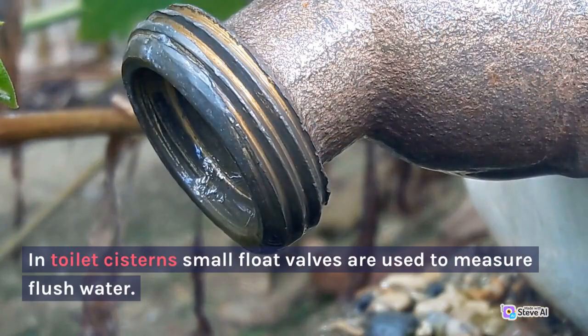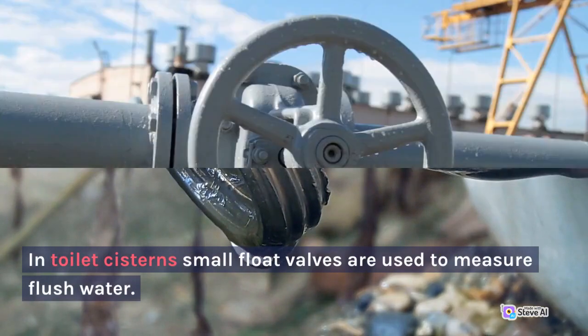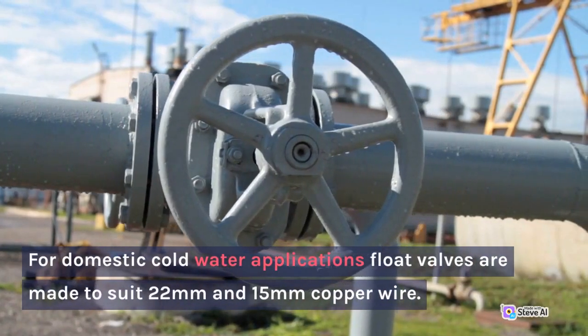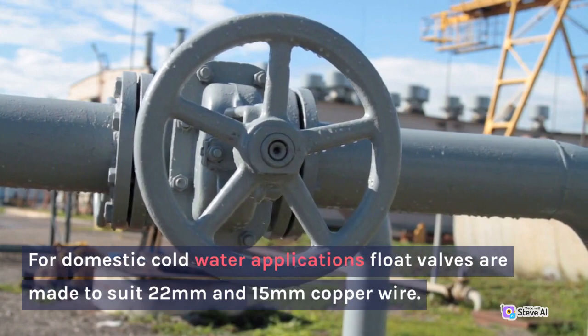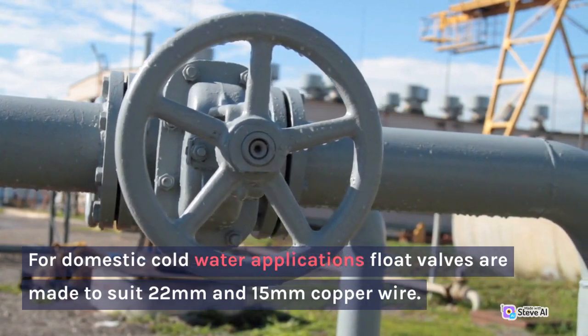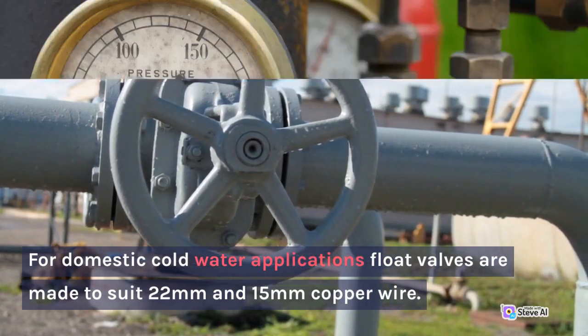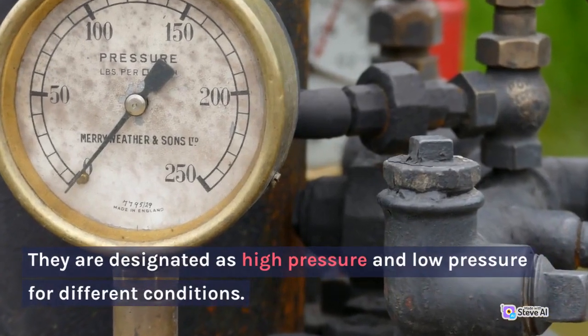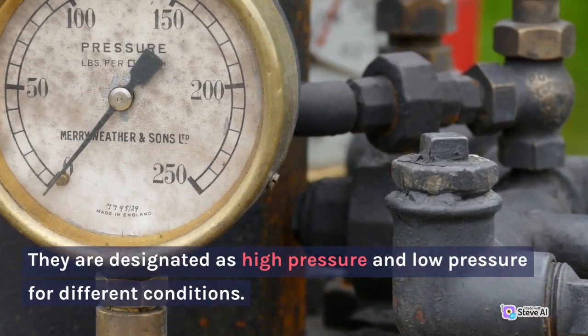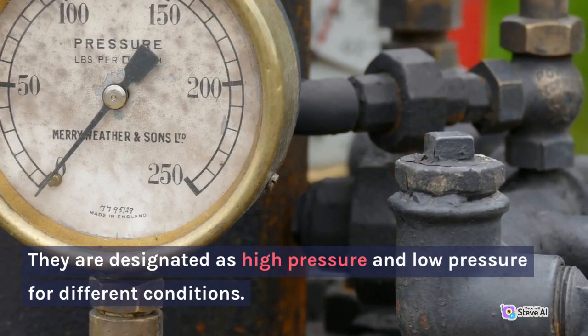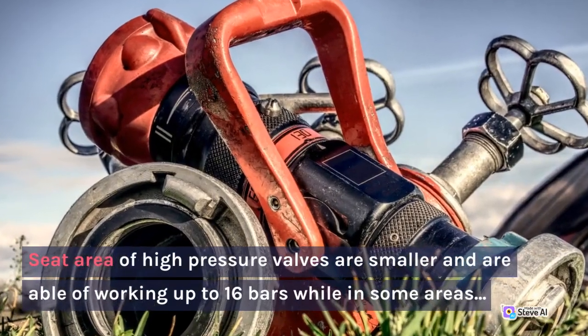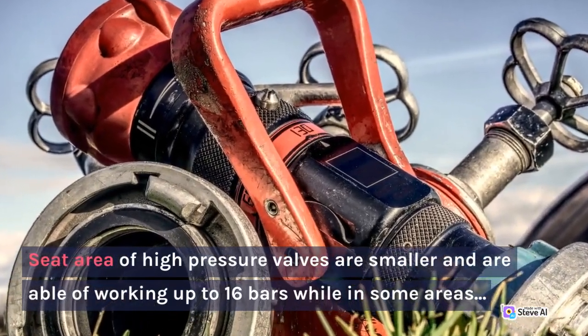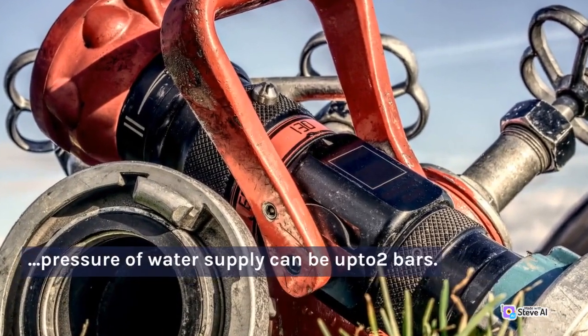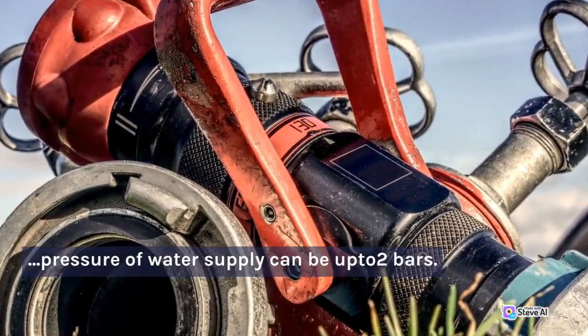In toilet cisterns, small float valves are used to measure flush water. For domestic cold water applications, float valves are made to suit 22 mm and 15 mm copper pipe. They are designated as high pressure and low pressure for different conditions. The seat area of high pressure valves is smaller and they are able to work up to 16 bars, while in some areas the pressure of water supply can be up to 2 bars.